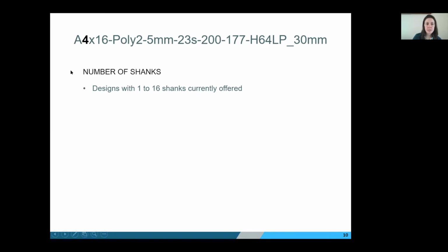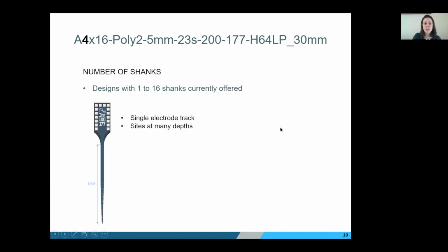The second piece of information is the first number in the model number, and that represents the number of shanks on the probe. So currently this probe would have 4. Currently in our catalog, there are designs with 1 to 16 shanks. Here's an example single shank probe. There's 1 electrode track, so it's a great transition if you're used to using single tungsten electrodes, and the mechanics of inserting this would be very similar, but you now have recording sites at many depths, so you don't have to move the probe as much to cover a wide range of a target of interest.